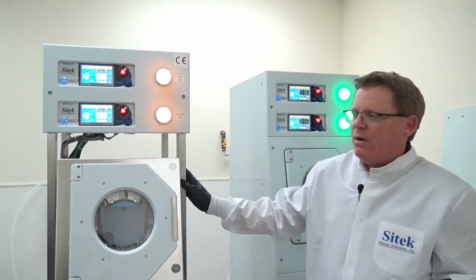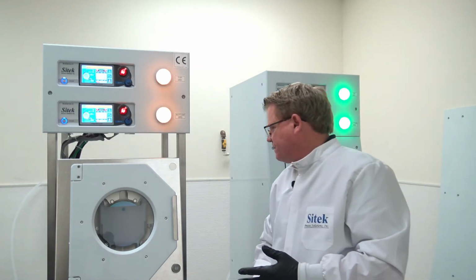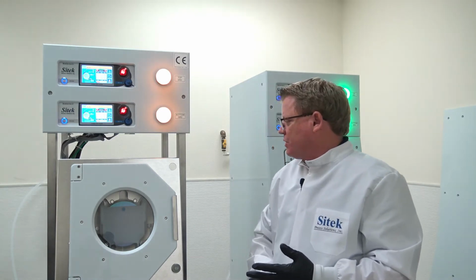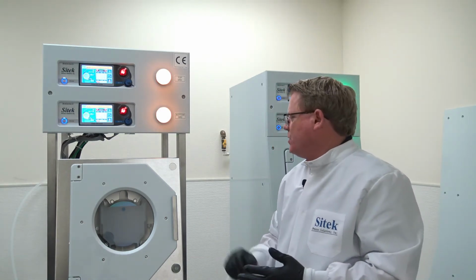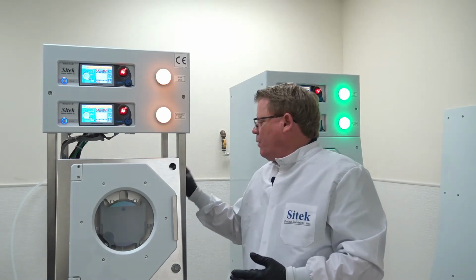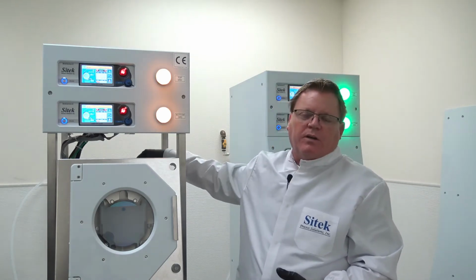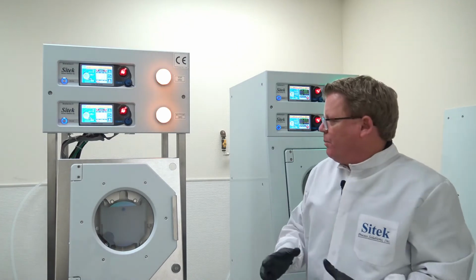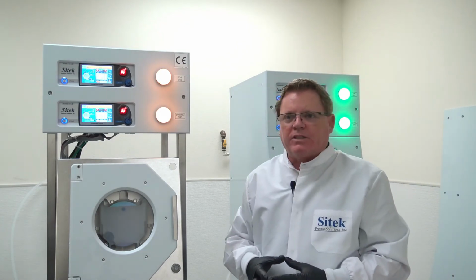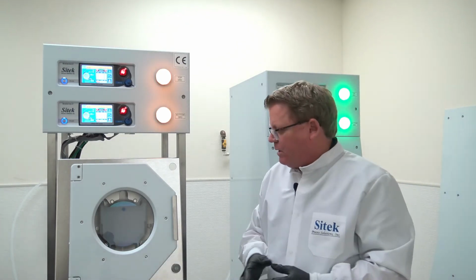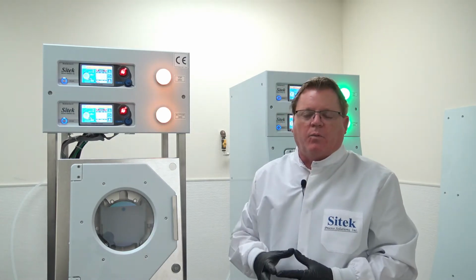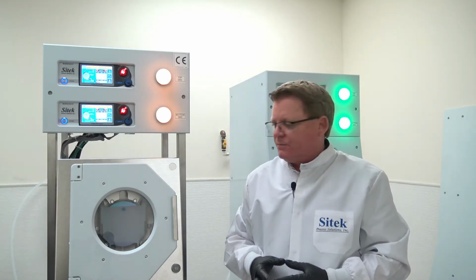Then we go through and rebuild the motor, rebuild the ACR valves, replace the Humphrey valves with SMCs. We rebuild the rotor stop positioner. We test or replace all of the 8 and 20 PSI sensors. We put new filters on. We then put in new Teflon lines for both N2 and DI. We put brand new pneumatic lines for the ACR valving and for all the doors. We replace the window and the window seal.